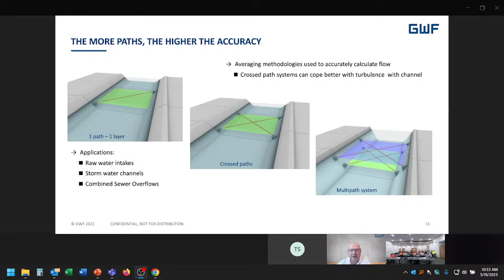So that's larger applications, but how does that cope with smaller channels? These types of systems are good down to say a 5-6 foot wide channel, but if you go smaller than that, or say you want to go into a manhole and look at a gravity sewer, what can you do to measure that? There are 2 ways of measuring: either with non-contact systems, Doppler systems like laser or radar, or we'll go on to wetted sensors in a minute.